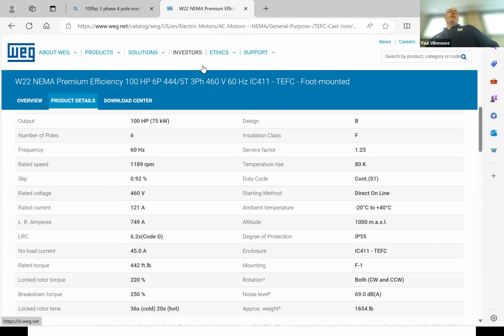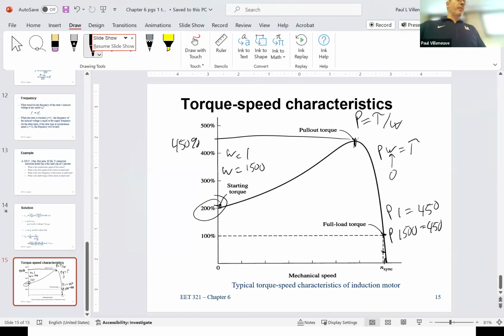Say you buy a motor rated 100 horsepower, but your mechanical engineering friends say they need 96.2 horsepower at, say, 1780 RPM. You'd just buy the 100 horsepower motor rather than design a custom 96.2 horsepower one—that would cost way more. On the performance curve, the design point might be here, but since you don't need that much power, you actually operate elsewhere on the curve. That's not a problem, since a custom motor costs far more, and you end up more efficient anyway. So as long as you have the space for it, you go for it.